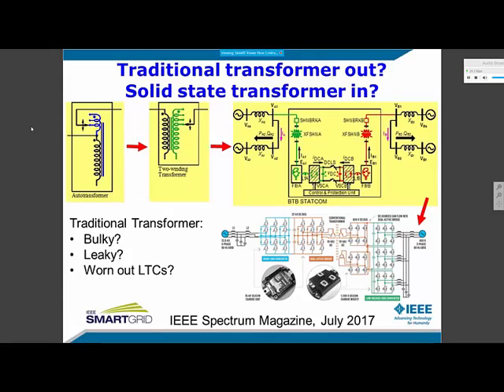Now, we could not use a regular transformer because a regular transformer has to work with one frequency. And here is a perfect application. Even though the cost is higher, we had to use this topology. So we took 2 inverters back to back and connected them at their DC terminals. The AC sides are connected with the 2 networks with 2 transformers.